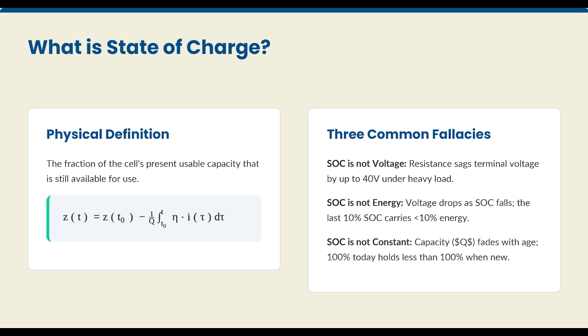The physical definition of SOC is an integral, but looking at the equation, it's really just a definition, not an algorithm. It assumes you already know where you started, that you know the capacity exactly, and that you measure current perfectly. Real hardware fails at all three of these, and that's where estimating the state of charge becomes more and more important. Charge cannot be directly measured, so we need to estimate it.